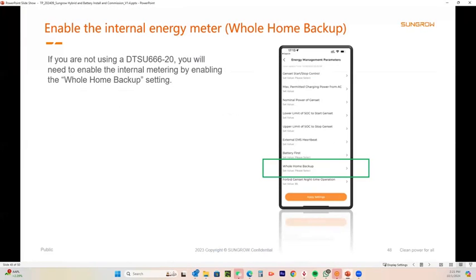We do have the Service Partner Program, but before I go to that, one last thing. When you do commission a system, now, the equipment that you've installed might have been manufactured maybe 6 months ago, okay? And during that time, we may have enabled more functionality, or we may have ironed out a bug, okay? So when you do a system at first, please always update the firmware as part of your commissioning. It can be done in the background on iSolar Cloud. We've got videos showing you how to do it. Make sure you update the dongle, the inverter, and if you've got a battery fitted, the battery. And you do that and it shouldn't be any problem.